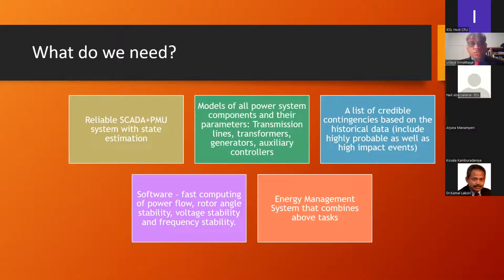You need software for fast computing of power flow, rotor angle stability, voltage stability, and frequency stability. These tasks can be done in parallel, because you can do power flow calculation quite independent of rotor angle stability assessment, voltage assessment, and frequency stability assessment. So they can be running on four different computers, or even more, because you repeat this for different contingencies.